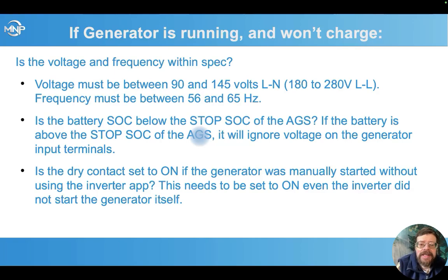Another thing to look at is, what are the settings for our AGS? If the battery is above the stop state of charge for the AGS, it's going to ignore the voltage on the generator input terminals. This is a common problem if we have a manually started generator and it still will only charge in between the stop and start settings on the AGS, even though you've manually started the generator.